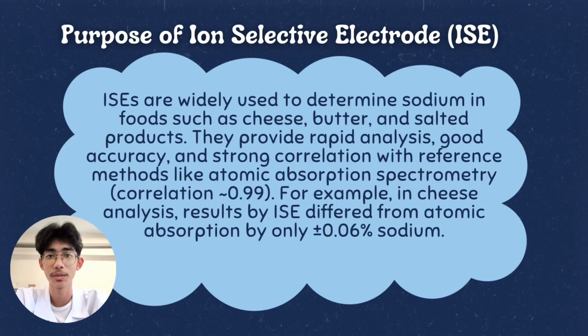So, what are the purposes of the ion selective electrode? ISEs are widely used to determine sodium in foods such as cheese, butter, and salted products. They provide rapid analysis, good accuracy, and strong correlation with reference methods like atomic absorption spectrometry, correlation 0.99. For example, in cheese analysis, results by ISE differed from atomic absorption by only plus or minus 0.06% sodium.